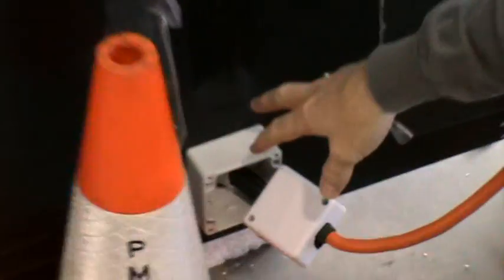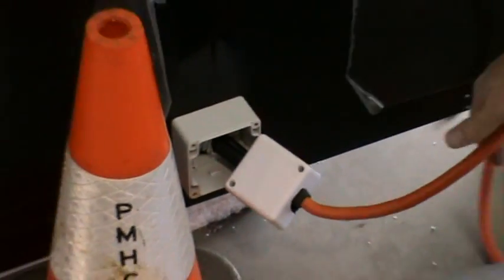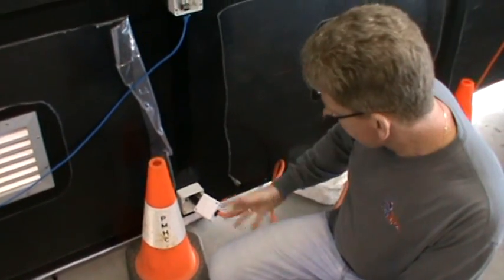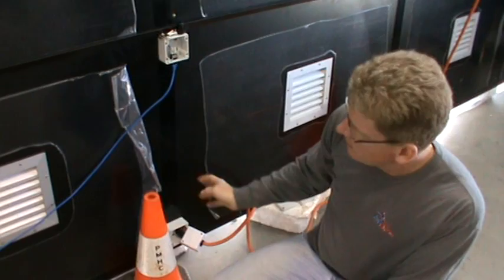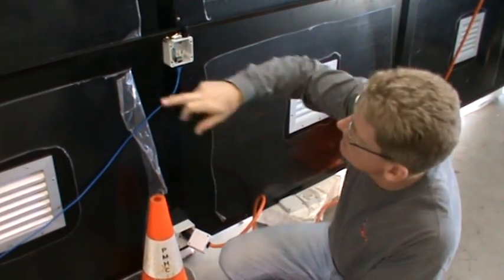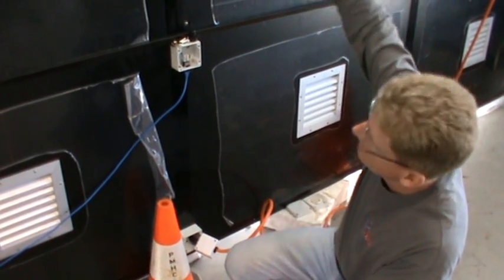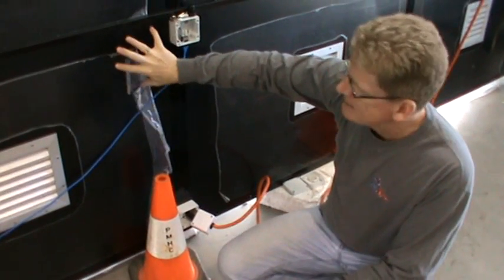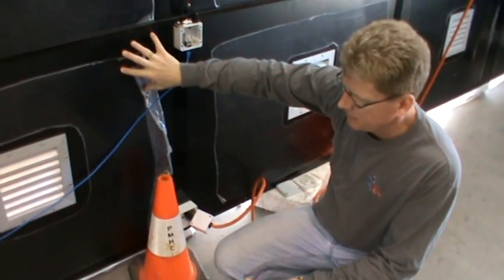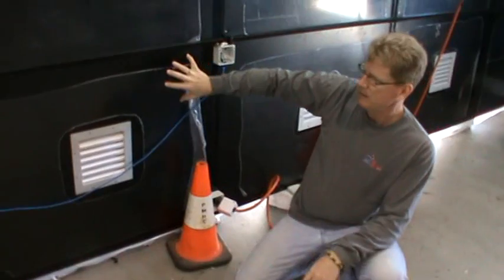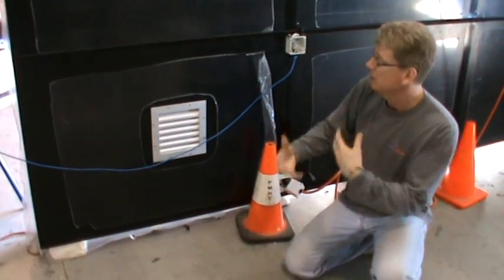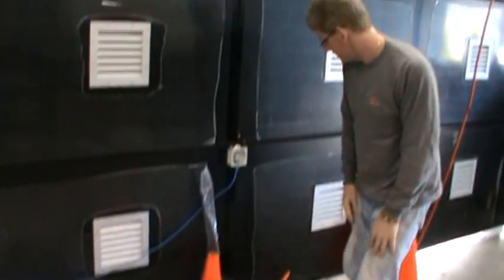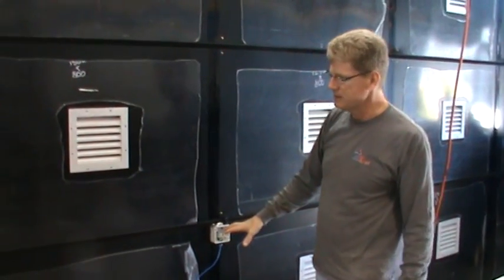Three-phase. This one in particular is a three-phase 32 amp connection, basically to a three-phase circuit. Very simple to wire when you get it. Essentially, you wire up your cables. With each cable run, you've got one phase running across each row of the cabinet modules. Inside these cabinets are all very weatherproof. We then cap everything fully with fans and everything on it, so we have good airflow when it's installed on site. Very simple to set up once it's there.